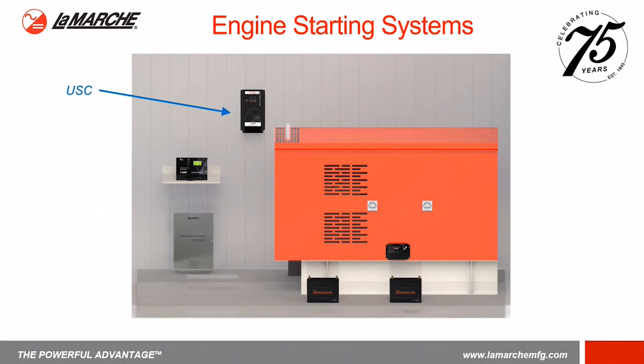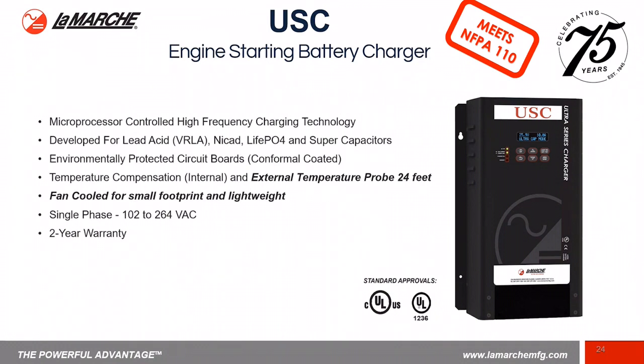The other charger that can be used to charge the hybrid capacitor modules is our USC. The USC is also a microprocessor high frequency charger. It can also charge lead acid, NiCad, or lithium ion hybrid supercapacitors. This particular unit is fan cooled, has temperature compensation, and can be mounted on a wall. It complies with UL 1236 and UL CUL. USC complies with NFPA 110, which requires you to have 4 alarm contacts: low voltage, high voltage, low current, and AC fail.